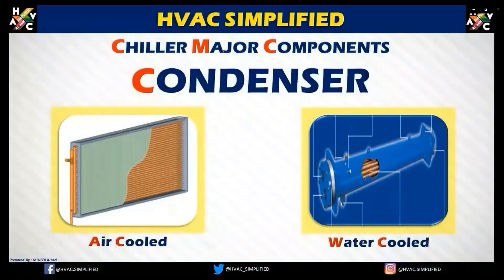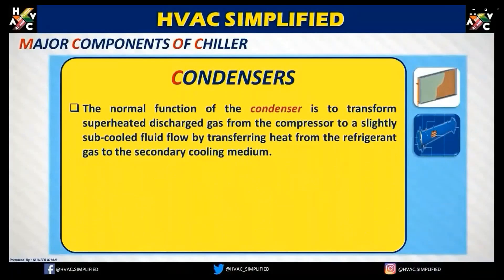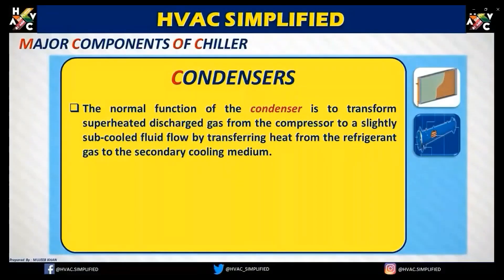The next major component is the condenser. Condensers are of two types: air-cooled and water-cooled. The normal function of a condenser is to transform superheated discharge gas from the compressor to a slightly subcooled liquid by transferring heat from the refrigerant gas to a secondary cooling medium. A condenser releases heat from the refrigerant — in an air-cooled chiller, it interacts with air; in a water-cooled chiller, it transfers heat to water.